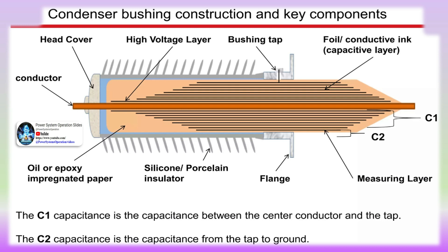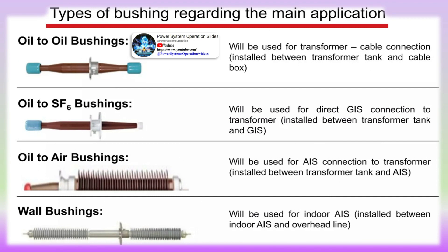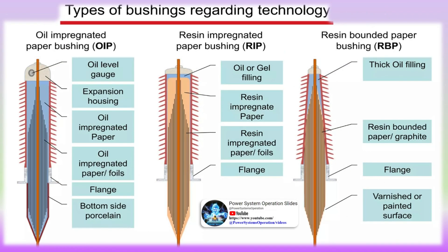The resistor Rs is used to limit the test tap voltage. The resistors may be located in the bushing monitor or in the bushing sensor. Locating the resistors in the bushing monitor allows for standardization of the bushing sensor design, since the same sensor can be used for almost all system voltages and bushing C1 capacitance values — the exception being extra high voltage (EHV) systems where additional protection elements are often required.